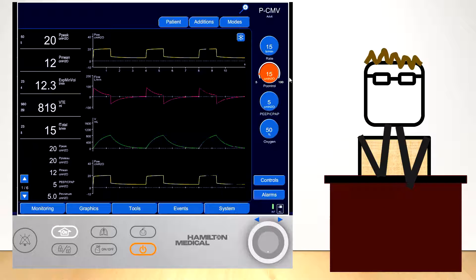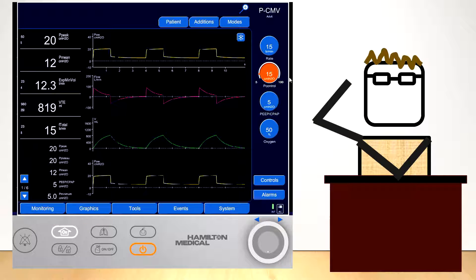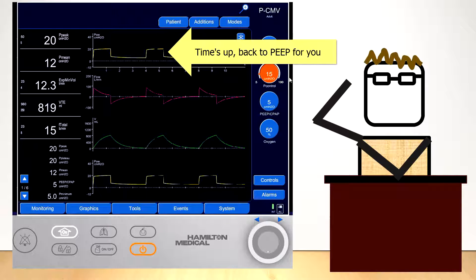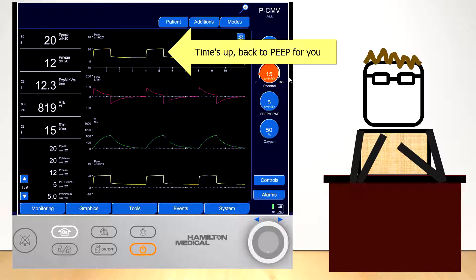Pressure Control Ventilation is time-cycled, which means that after a preset time, the ventilator drops the airway pressure to a set PEEP to allow for exhalation.